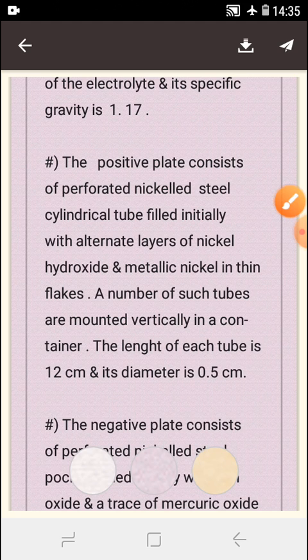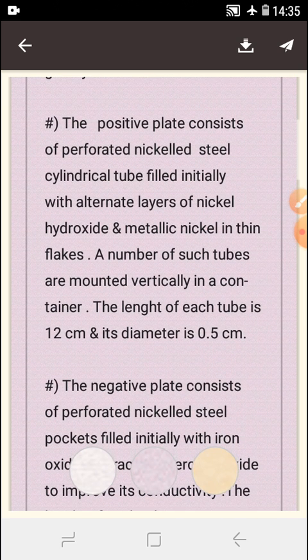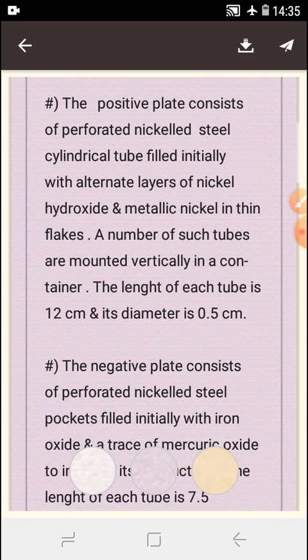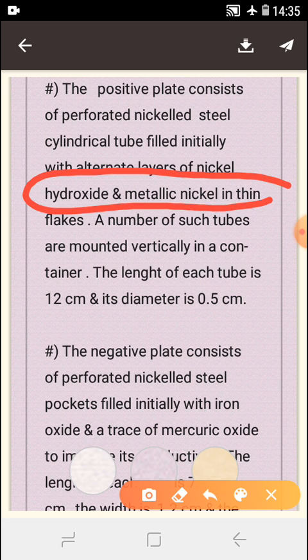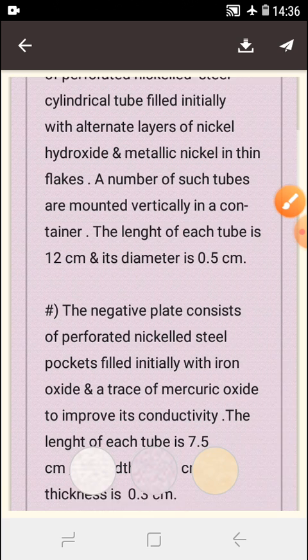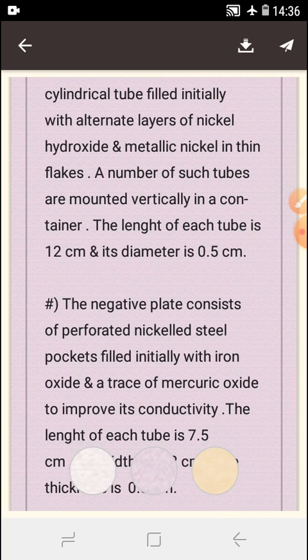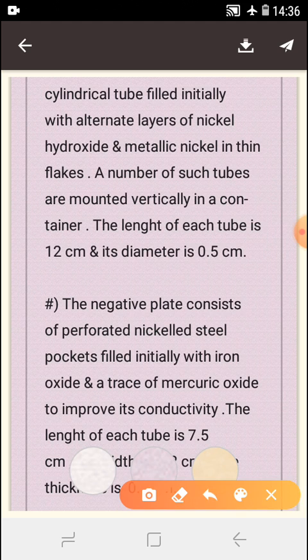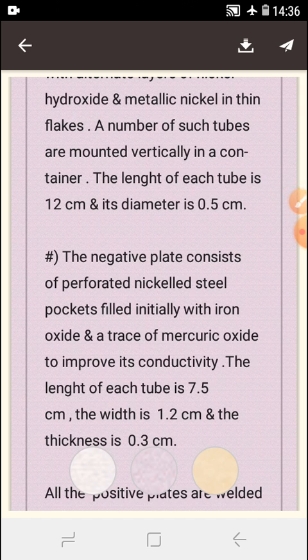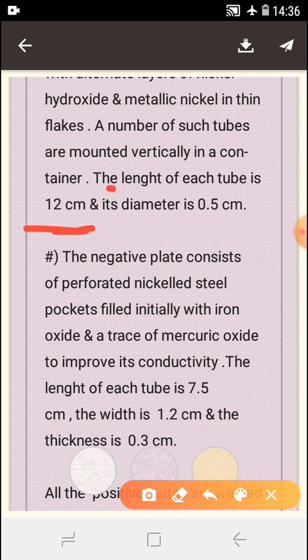The positive plate consists of perforated nickel steel cylindrical tubes filled initially with alternate layers of nickel hydroxide and metallic nickel in thin flakes. A number of such tubes are mounted vertically in the container. The length of each tube is 12 centimeters and its diameter is 0.5 centimeters.